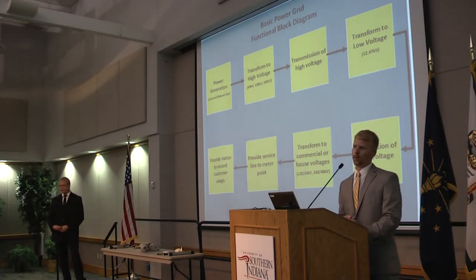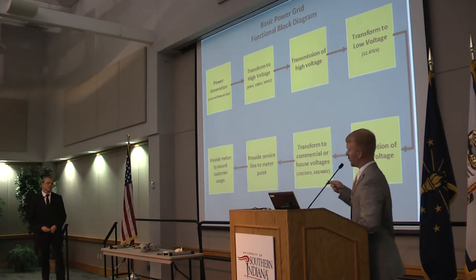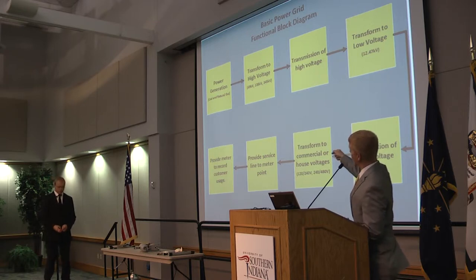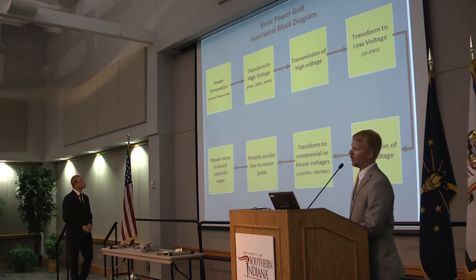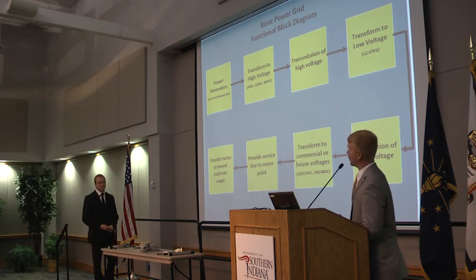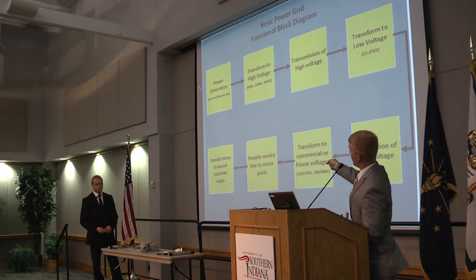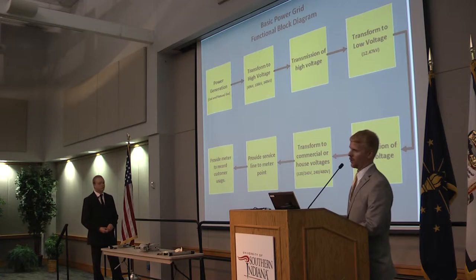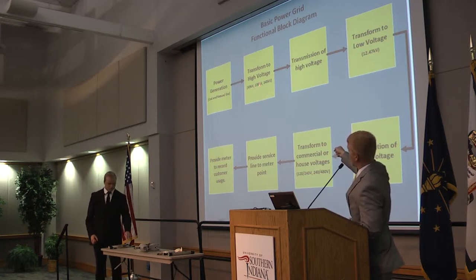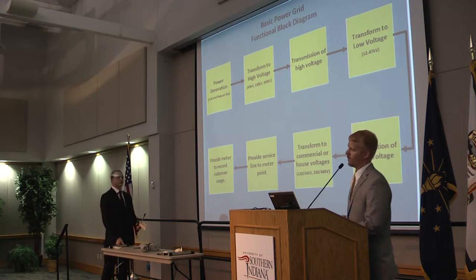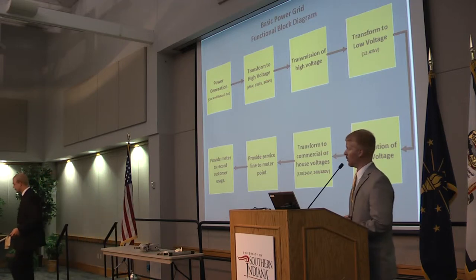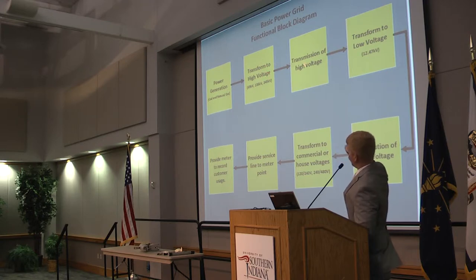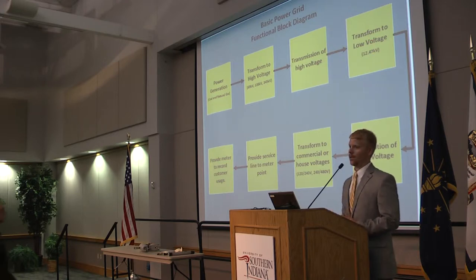So to dig in a little bit more on what the power grid is, this is a functional block diagram of the power grid. Starting out at power generation is the power plant itself. It's usually coal and natural gas fired, a turbine at the power plant. Outside of the power plant is a substation where it transforms the voltage off of the turbine into 69,000, 138,000, or 345,000 volts in the Vectren system. Those are the standard voltages. From there, it is sent through transmission lines across the Vectren area. At a certain point, when the load is necessary, we put in a substation.